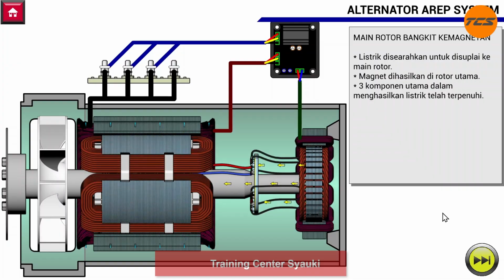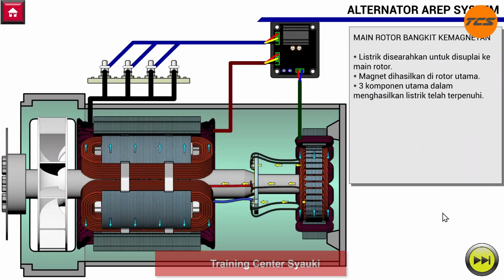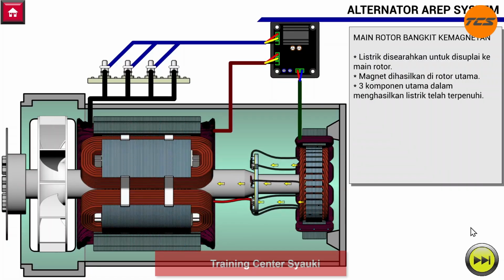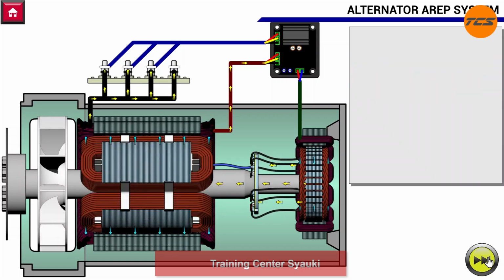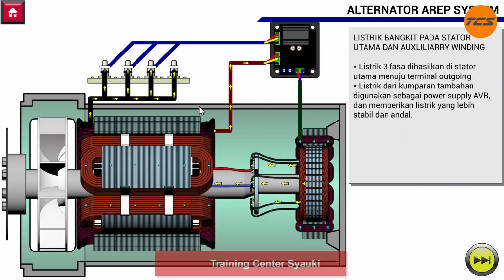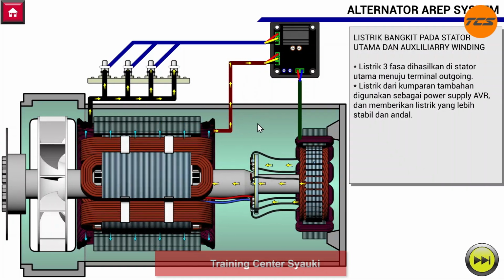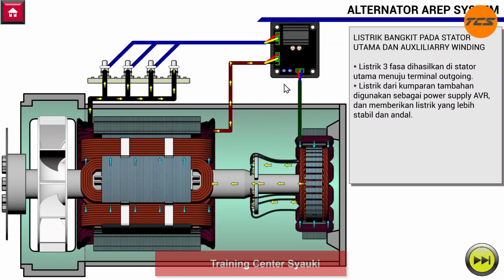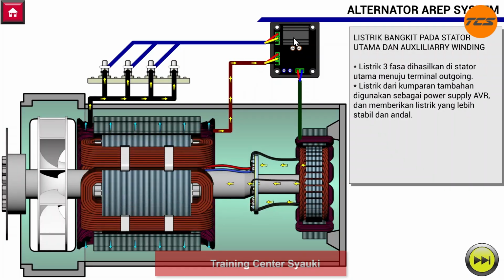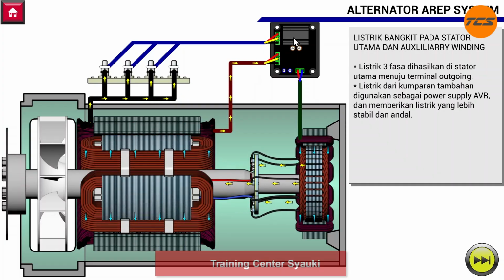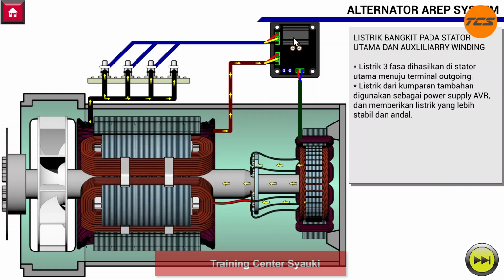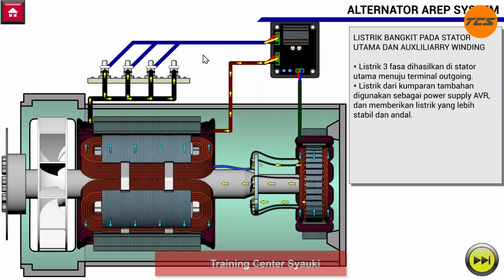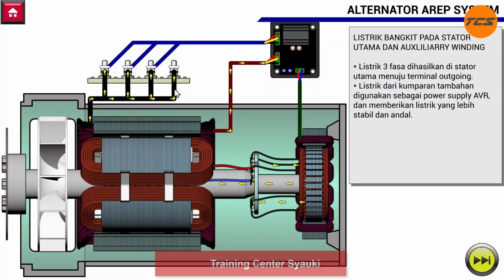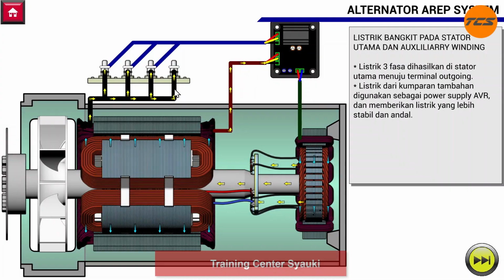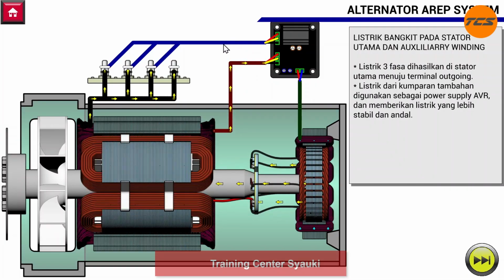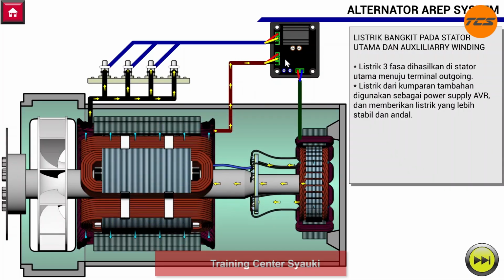As the magnetic field in the main rotor strengthens, it is cut by the winding in the main stator, causing voltage to be induced in the main stator winding. Inside the main stator, there are actually two types of winding. Number one is the main output winding, which produces three-phase output voltage for the load. And number two is the auxiliary winding, which supplies power to the AVR. The voltage from the auxiliary winding is sent to the AVR as a power supply. And the output from the main stator, or main winding, acts as a sensing voltage. In some generator designs, a transformer is installed between the terminal and the AVR to reduce the sensing voltage to a suitable level for the AVR.